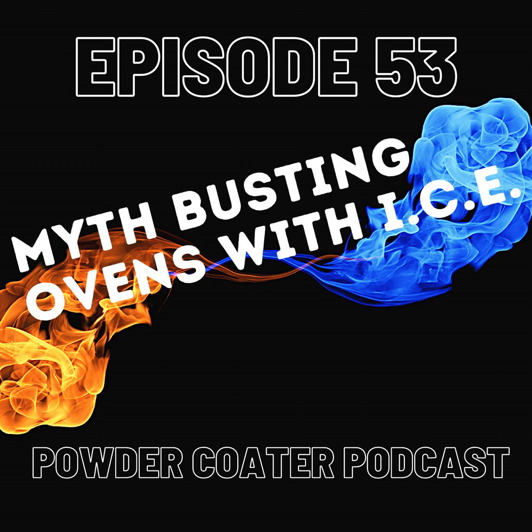Now in some bigger ovens, by code, you have to turn over the air in the oven so many times before technically you're allowed to put gas to it. So there is a purge cycle that by code you have to go through, and typically they like to see about 10 minutes. If you have a large oven, that means you need a pretty large exhaust fan. To reduce the purge time, we can put a bigger fan in, and then once we get through the purge, we can slow it down with the VFD so we're not pulling all that extra air out. So that's another reason it gives us flexibility.